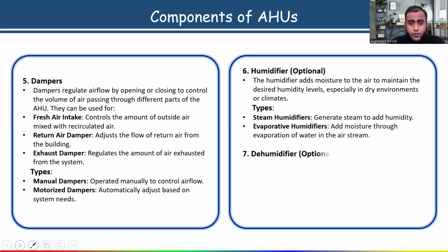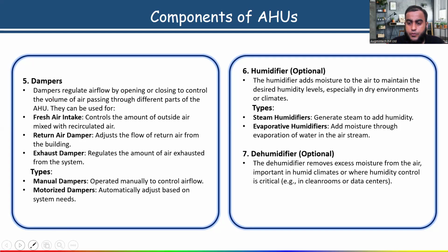Different types of humidifiers are there: steam humidifier and evaporative humidifier. In the same way, a dehumidifier is also given, and that is optional. Suppose in some location you have a high humidity level, more than 50 or 55%, let's say 70 or 80% relative humidity. In that environment we have to install a dehumidifier, because it removes the excess moisture from the air. Different types of dehumidifiers are there, which we will discuss here. A dehumidifier removes excess moisture from the air, which is important in humid climates or where humidity control is critical, for example in clean rooms, data centers, and more. Is it clear?